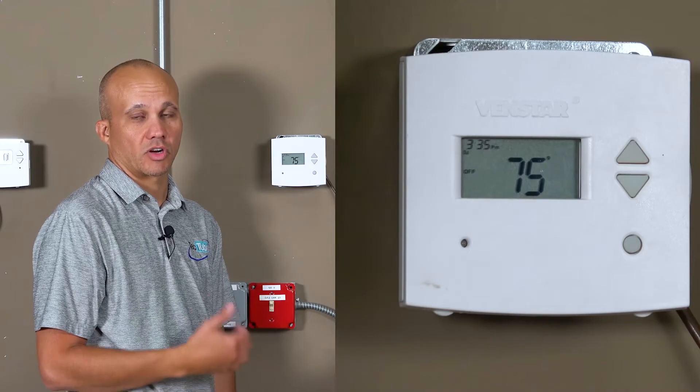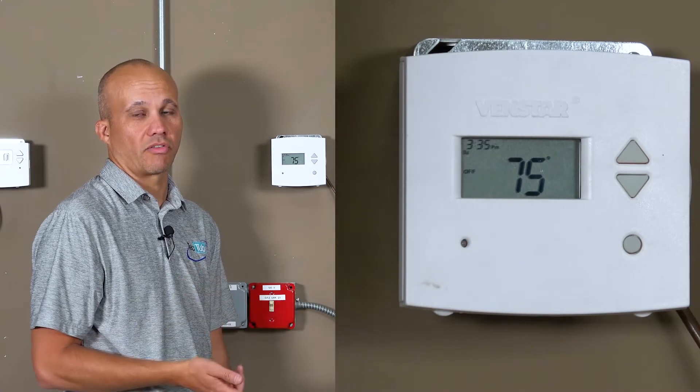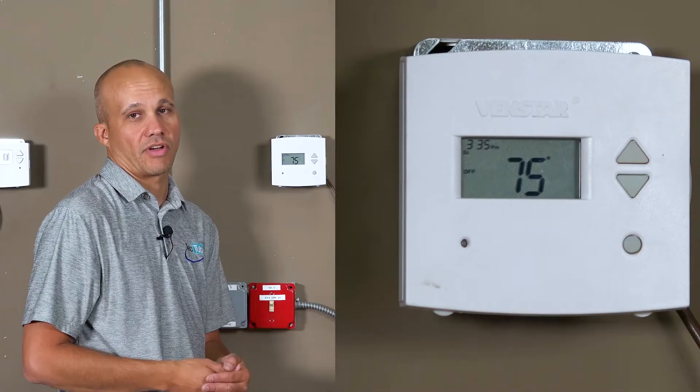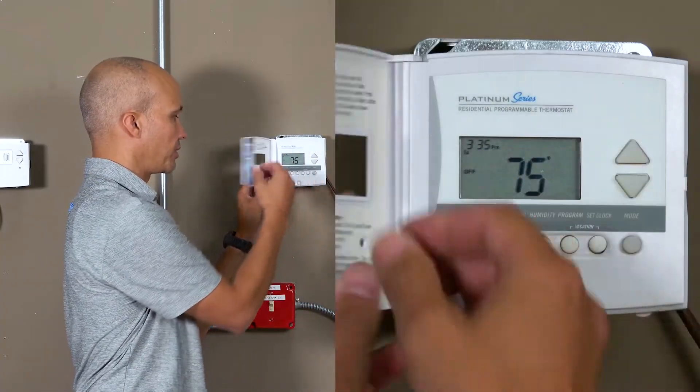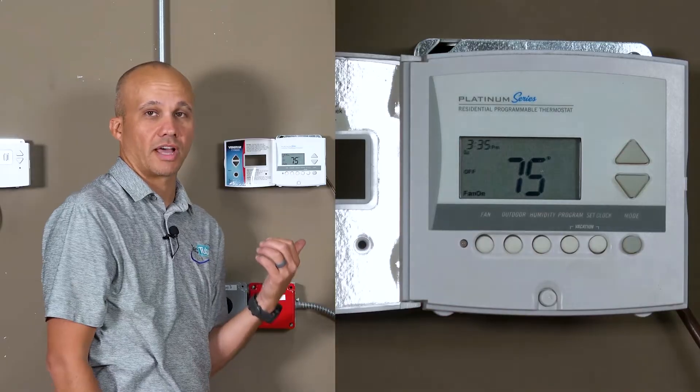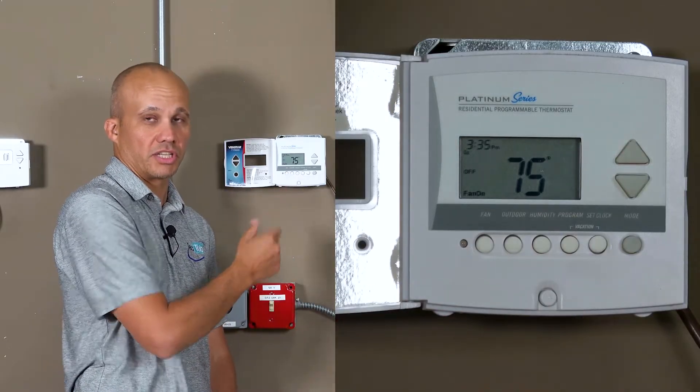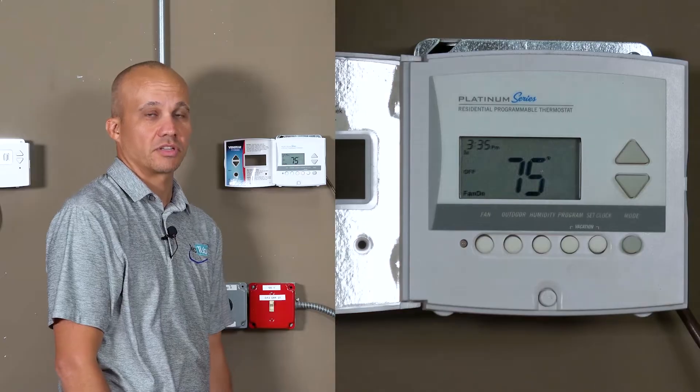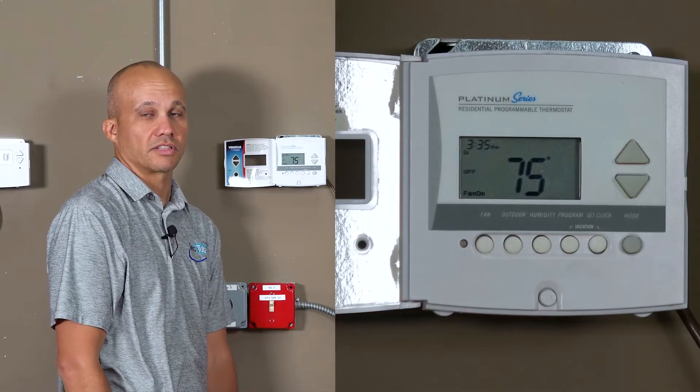Creating a call from the thermostat to request the equipment to provide heating, cooling, or fan depends on the kind of stat you have. In this particular case we open up the door and we simply press the fan on button and now the fan will turn on. So the thermostat just made the connection between R and G which energizes the fan upstairs. So we can go upstairs and see what our meter tells us up there.